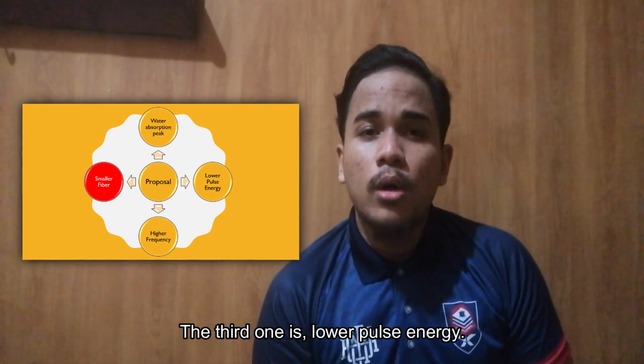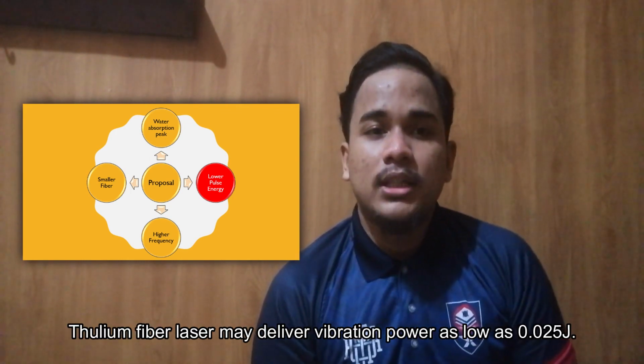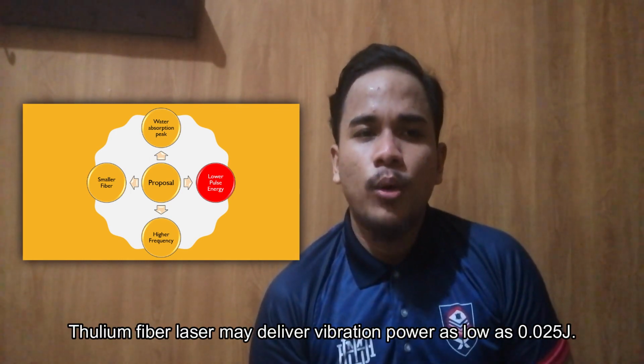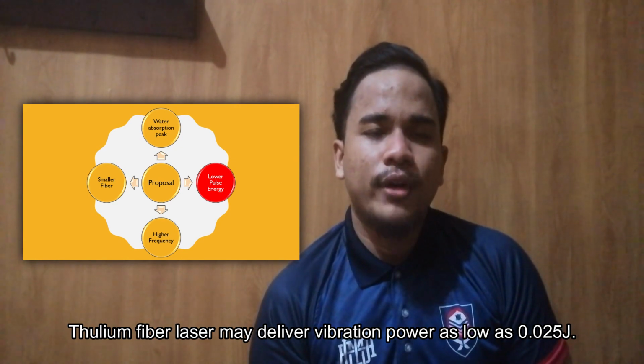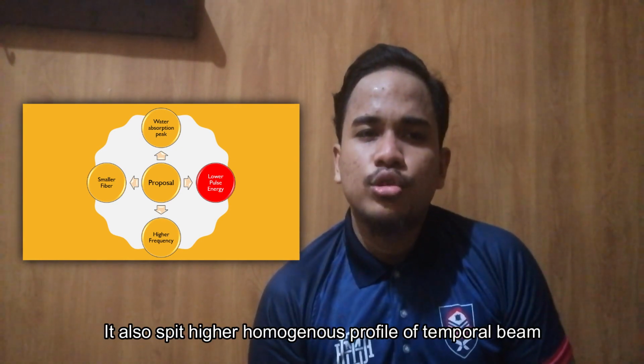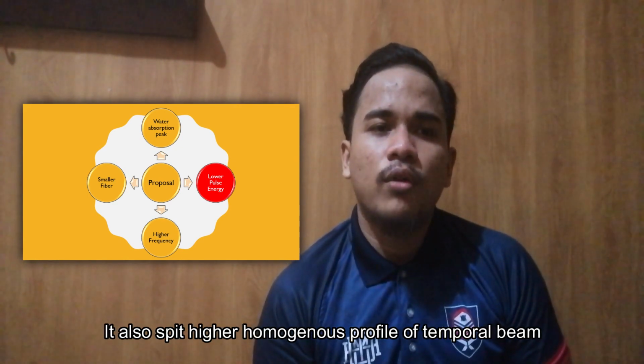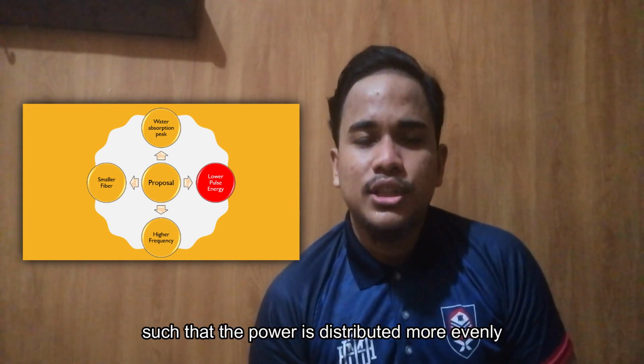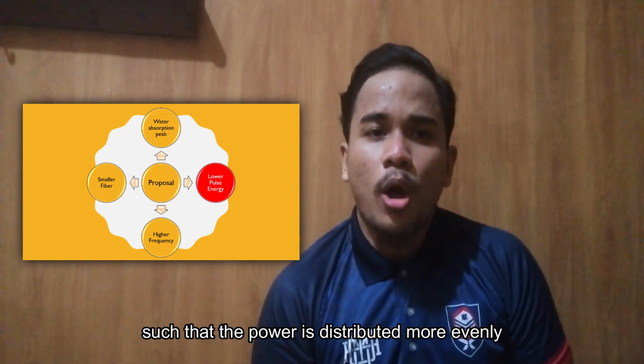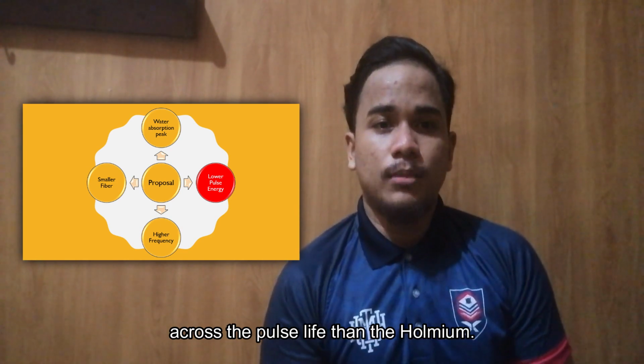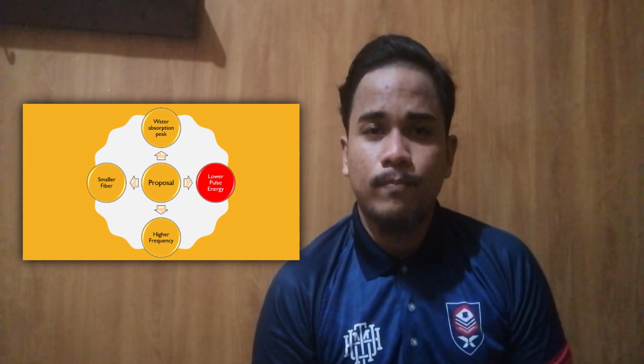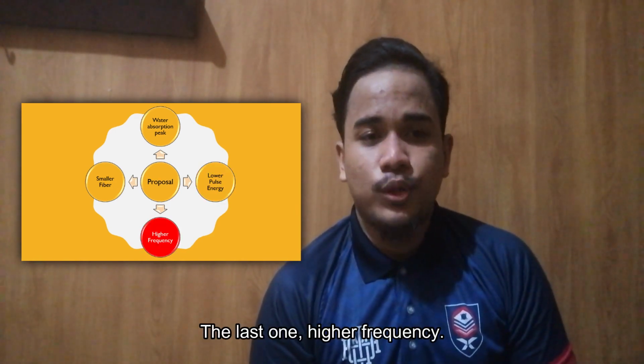The third one is lower pulse energy. Thulium fiber laser may deliver pulse energy as low as 0.025 joule. It also has a higher homogeneous profile of temporal beam, such that the power is distributed more evenly across the pulse life than the holmium. The last one, higher frequency.